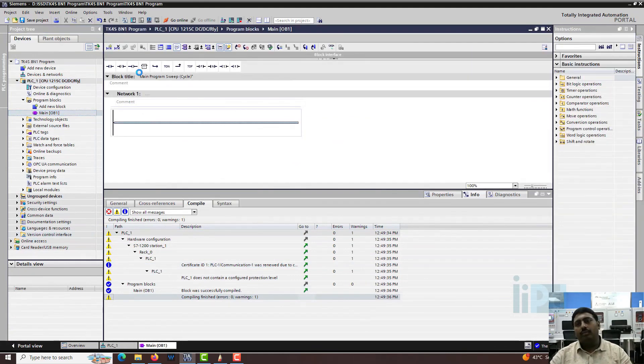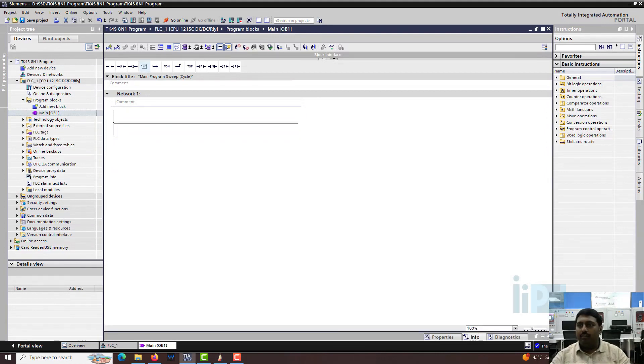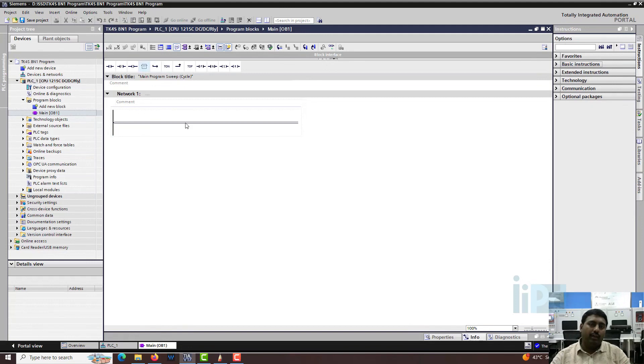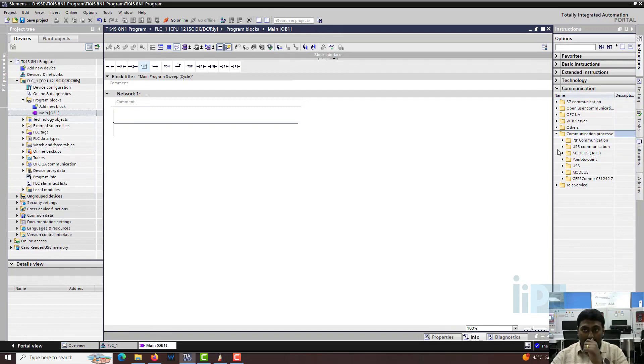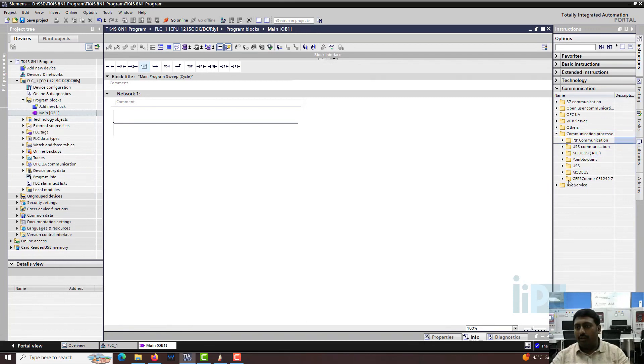Let's go to the main block and start the programming. We need to first enable the Modbus master block. For that, go to the communication processor under the communication instruction tab, go to Modbus - not Modbus RTU or P2P - go to Modbus and select MB_COMM_LOAD.